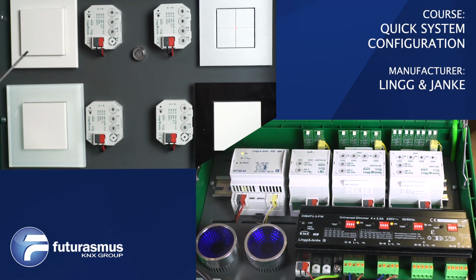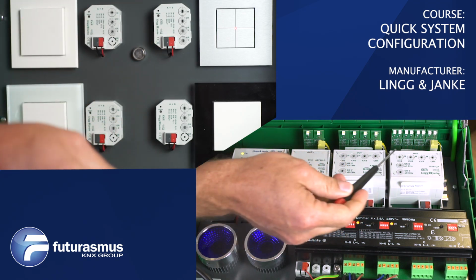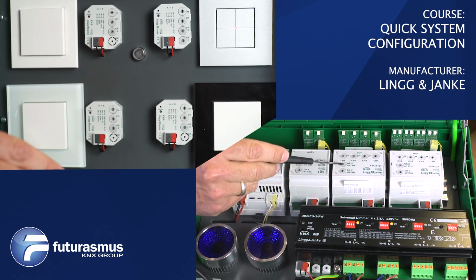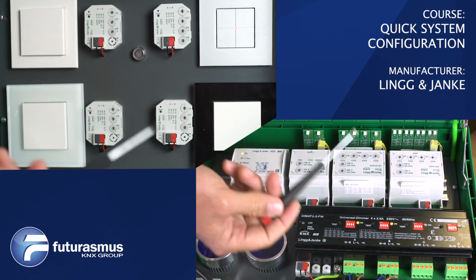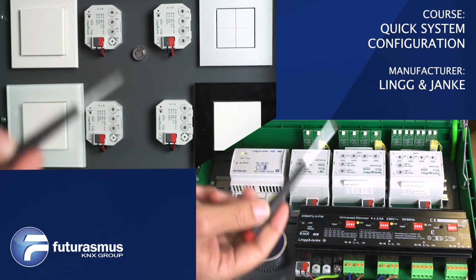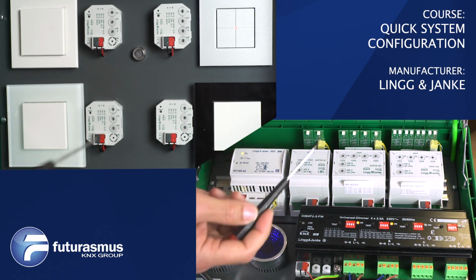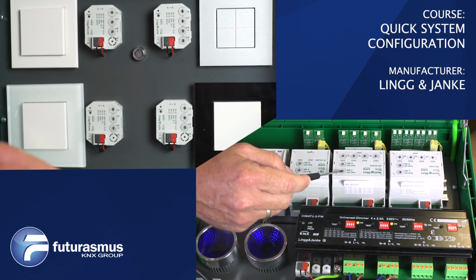Now let's say we want, with this push button here, to switch on all the channels and switch off all the channels. But you don't want to lose the on-off functionality of the first button. This one should still be able to switch on and off the channel. That's why you will use the Y. The Y is for the second group address, which you will be sending, if you know what I'm speaking about. If you don't know about KNX, don't worry. That's the second addressing feature which you have here.